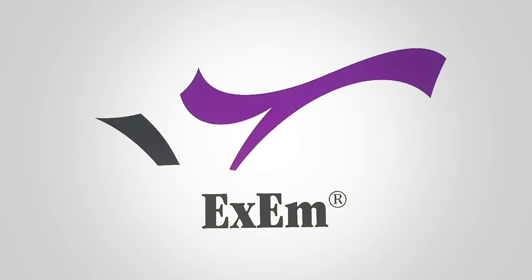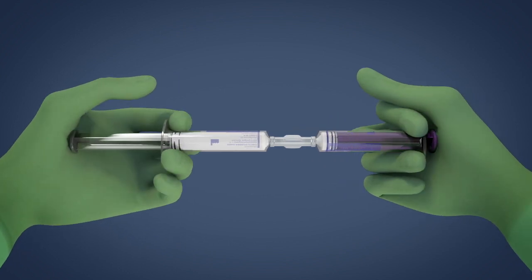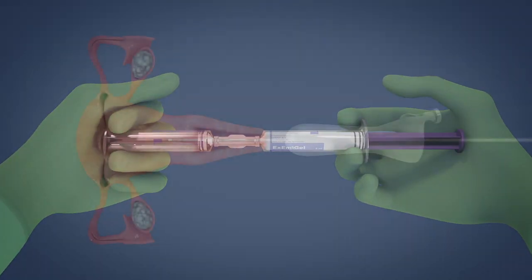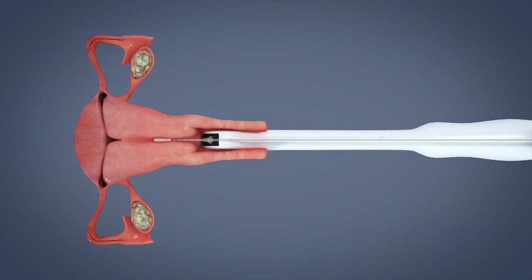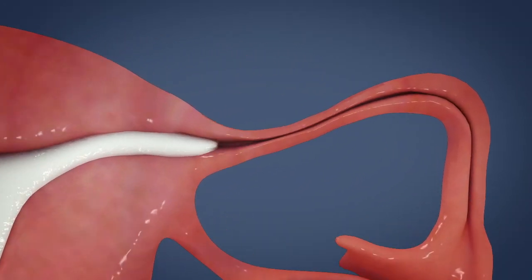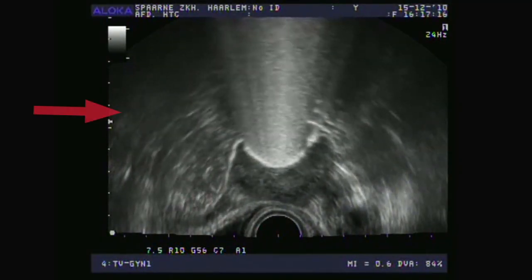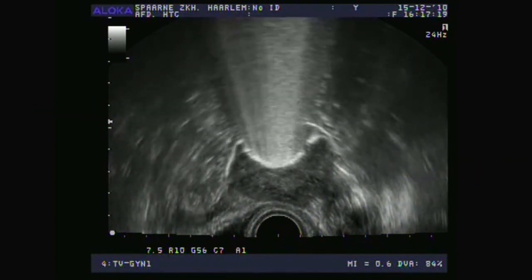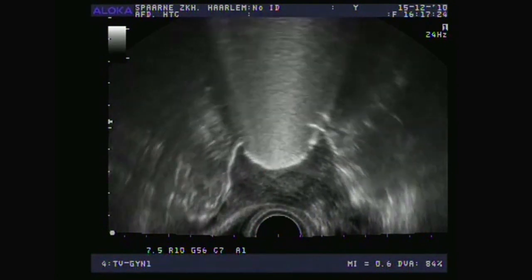The ExEm Foam Kit enables easy and safe recognition of tubal patency. By diluting the ExEm gel with ExEm water, a gel foam is created which enables a fast and simple distension of the walls of the fallopian tubes. The gel foam opens the tube from its natural collapse state and flows unless there is an obstruction. The ability to infuse the foam is an indicator of patency. Patency can then be confirmed using ultrasound imaging to detect the presence of the foam running the length of the tube.